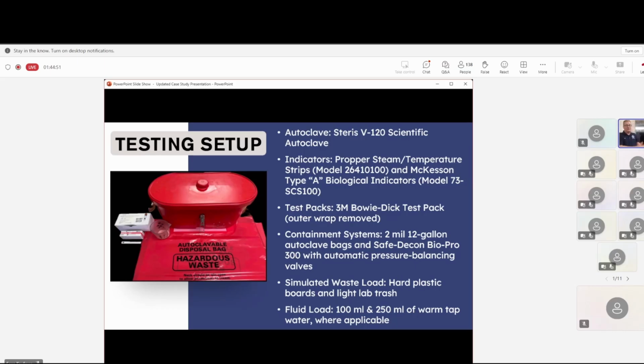You'll see that this is my autoclave here that you see behind me. I have an older version, a Steris V-120 autoclave. Now, for the indicators, I use two of them. I use the Propper steam temperature indicators. These are 121 temperature strips, and they detect steam and heat. If it hits it with steam or just heat, they won't go. It has to be steam and heat.